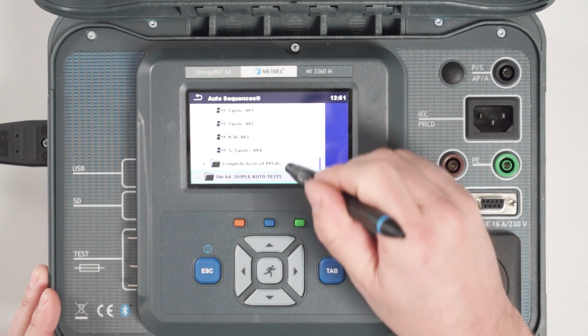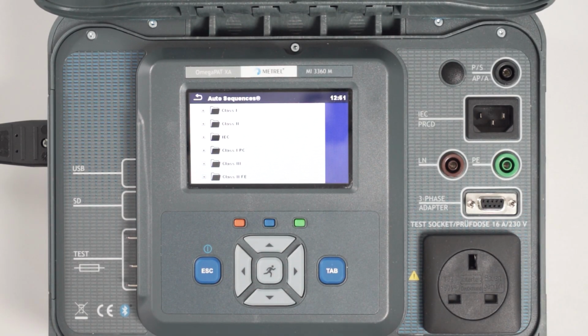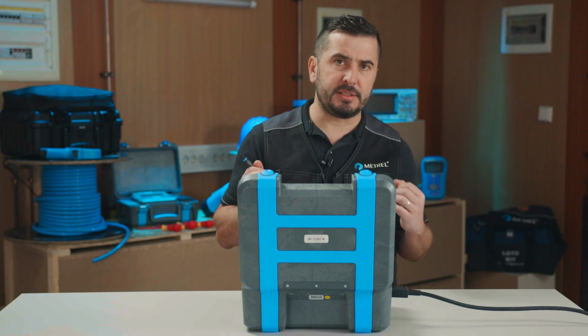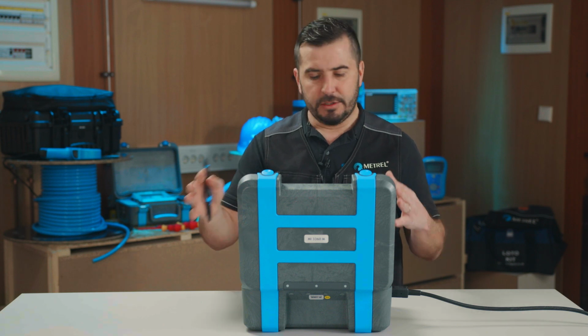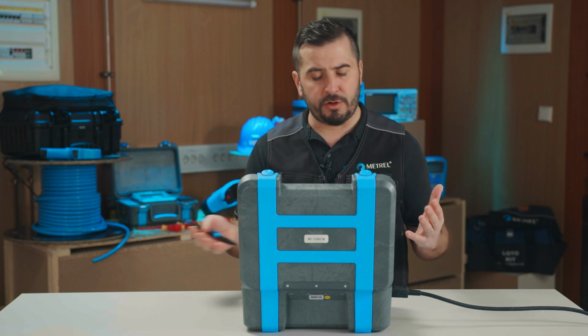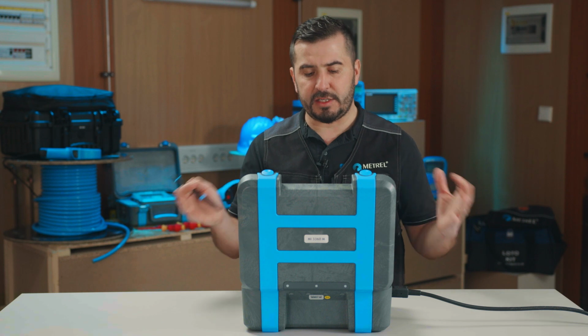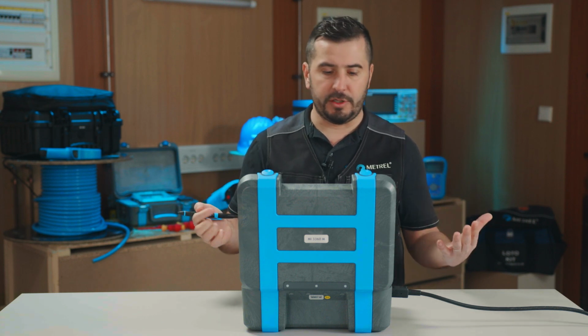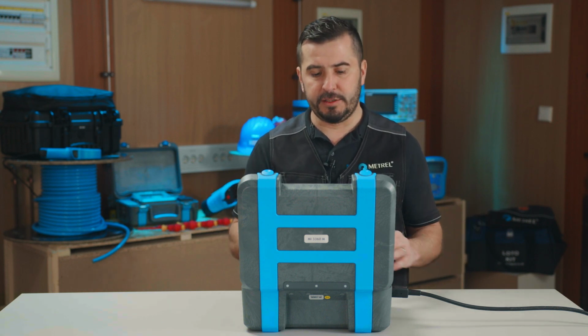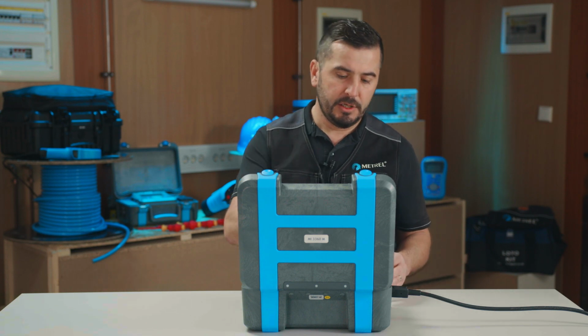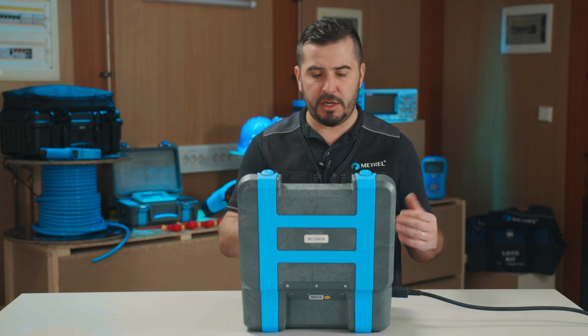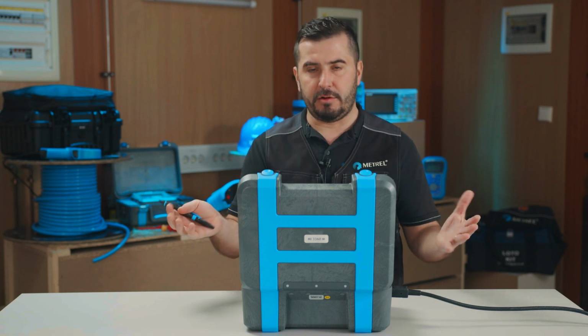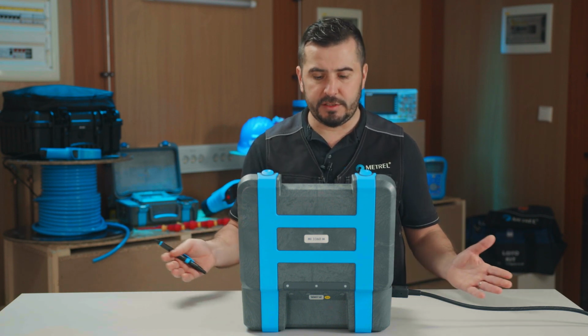And the last group is for those who do not like to think too much about what kind of group the appliance would fit in, but they just know that the appliance is either class 1, class 2, whether this is an IEC lead, or a PC, class 3, or class 2 with functional earth. We have inside here a couple of auto sequences which can be simply selected with one click and start, and our appliance will be tested accordingly.